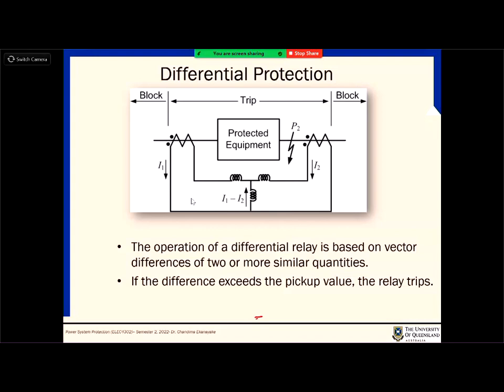But it is quite a simple technique, and when you implement it, you need to consider a couple of factors, as an example, turns ratios of the CTs and the direction of these windings. Those are quite important parameters to be considered, right? So in this sort of arrangement, we look at the magnitude of this leakage current, right? Usually 0 is not a good number. You don't say that if the current is above 0, it should operate. We don't do that, right?